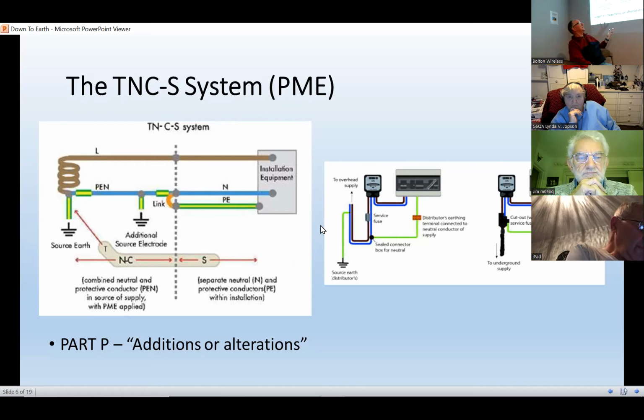Well, what's the point of all this, you may say? Well, let's suppose you decide to go out into your back garden and you hammer in a great earth spike because somebody has told you you've got to have an earth connection, otherwise your HF radio is not going to work very quickly or very well. And then you decide, well, for safety's sake, I ought to bond that to the rest of my electrical installation. So you connect it to the earthing terminal in your house. Okay, nothing bad there particularly.